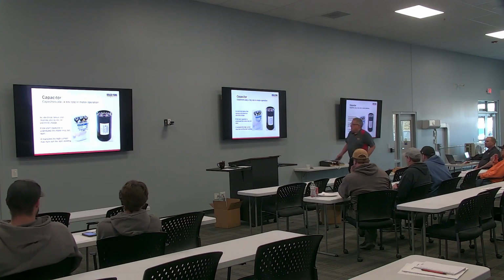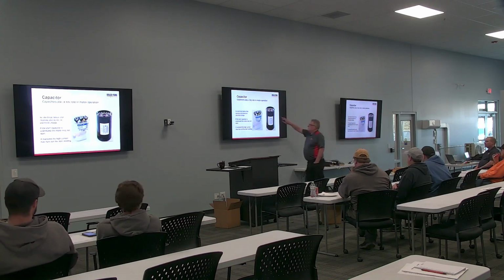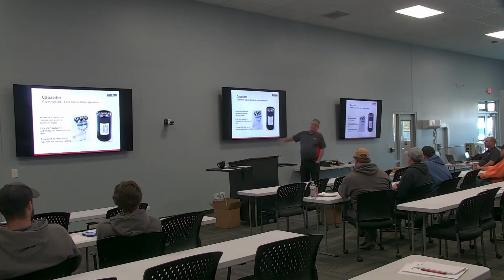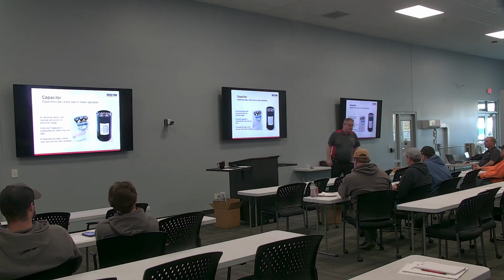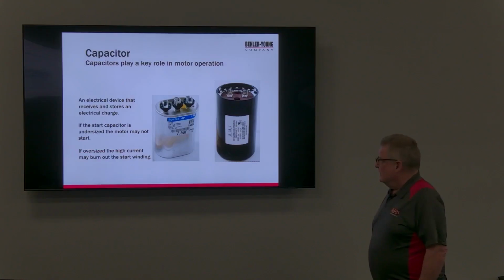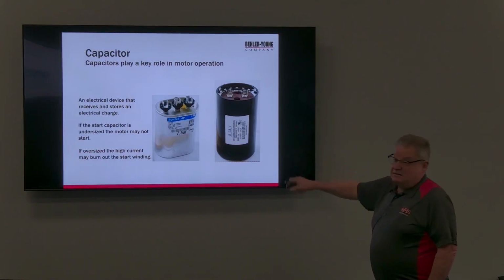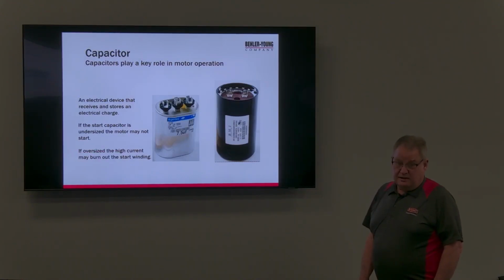So, we want to discharge start capacitors. That resistor up there, that's what it's for. It's to bleed the voltage off of those. It lengthens the life of the relay. But even the little run capacitors, they hold a charge. Shut the power off, take your screwdriver, short across terminals before you touch them.